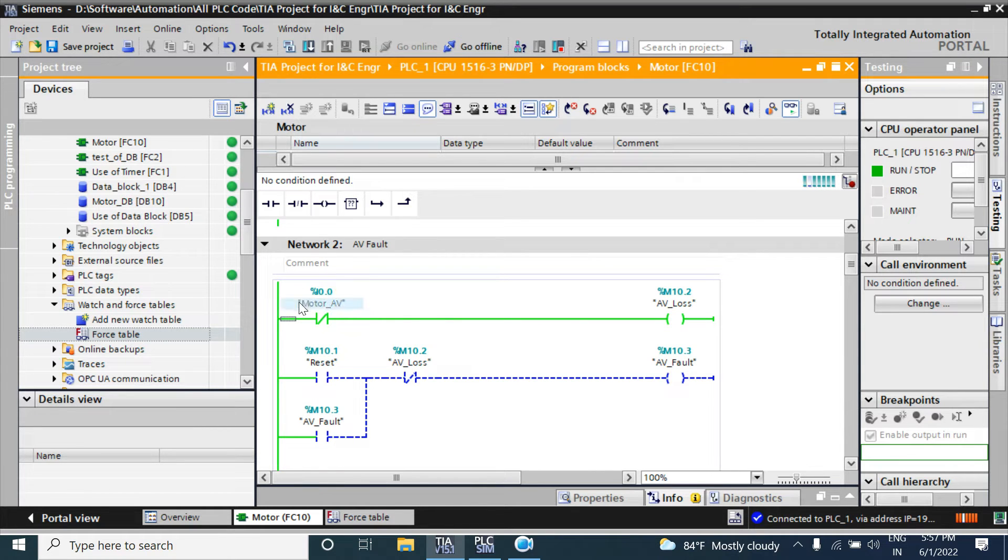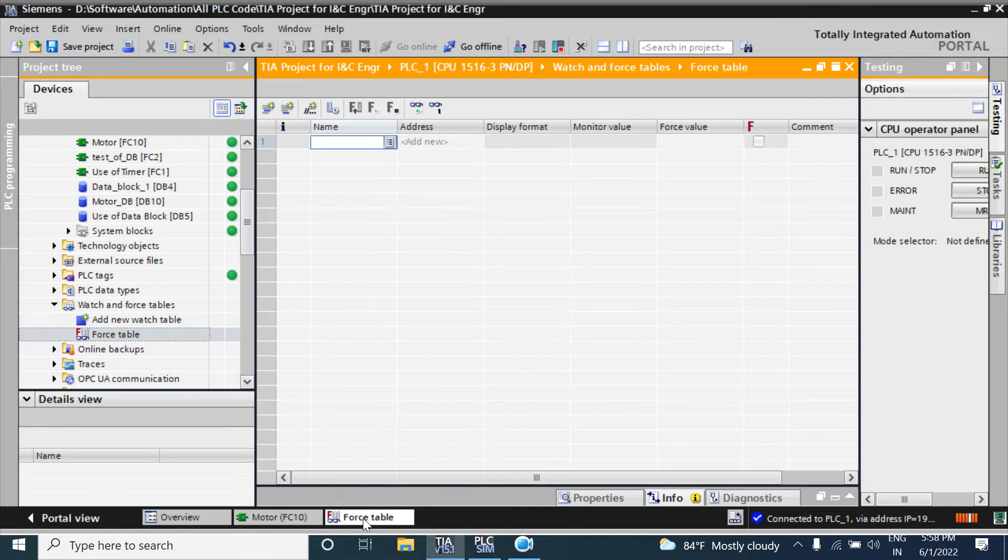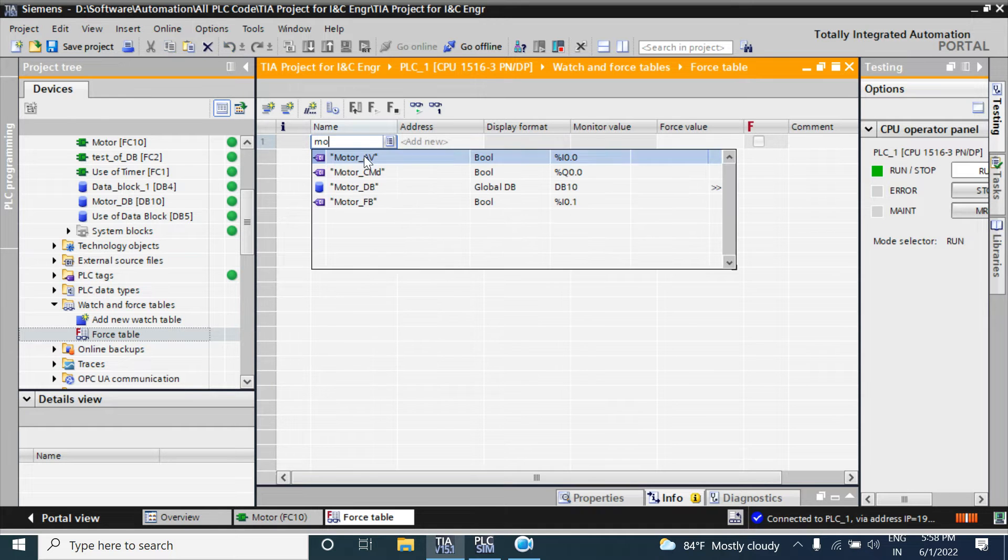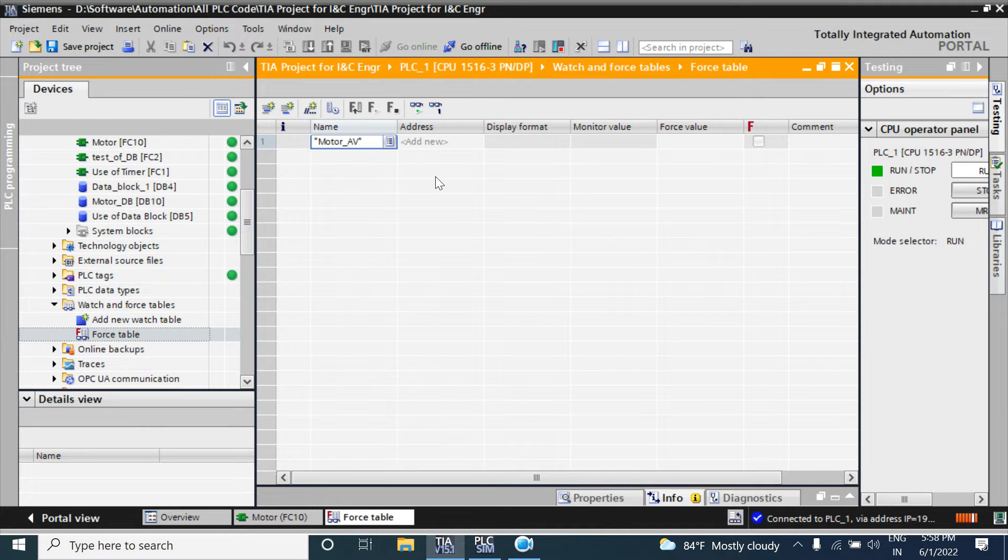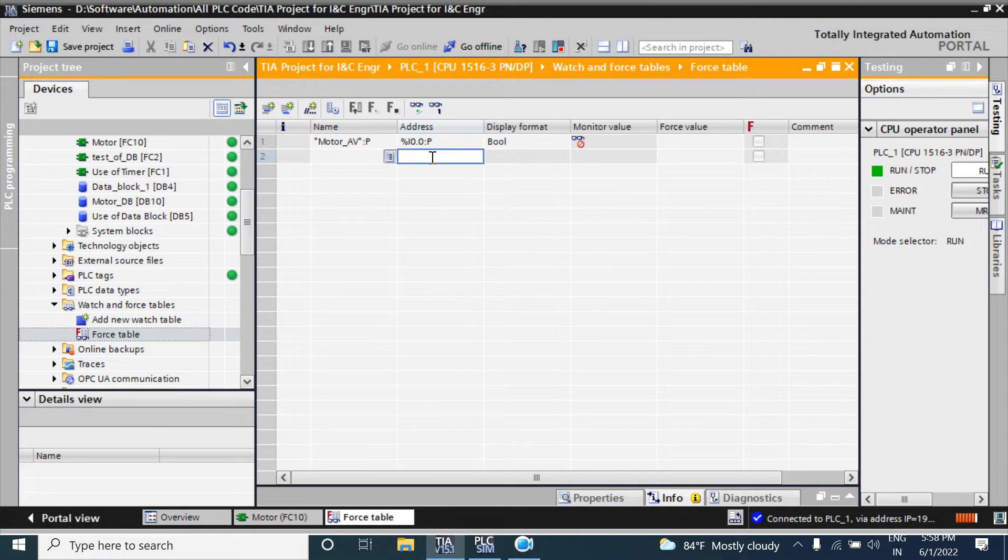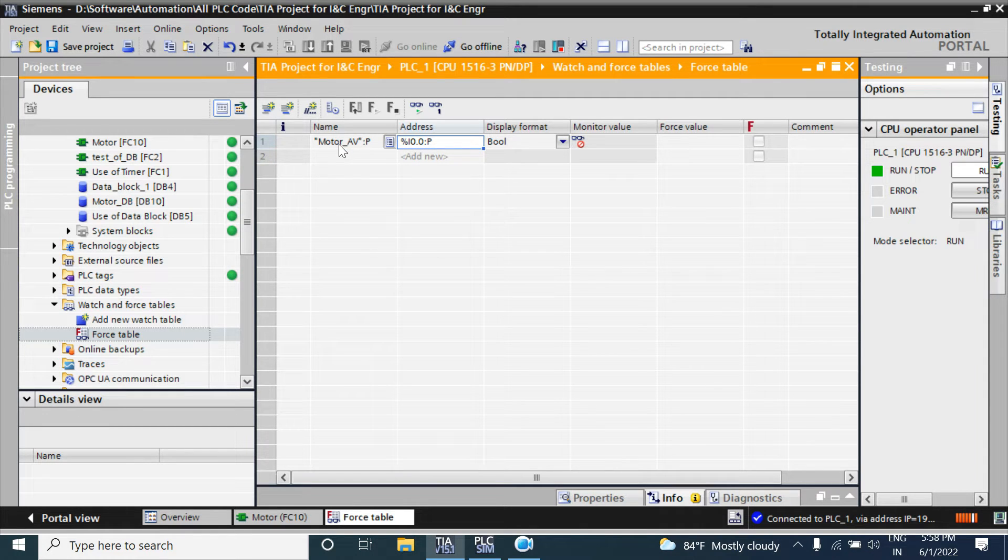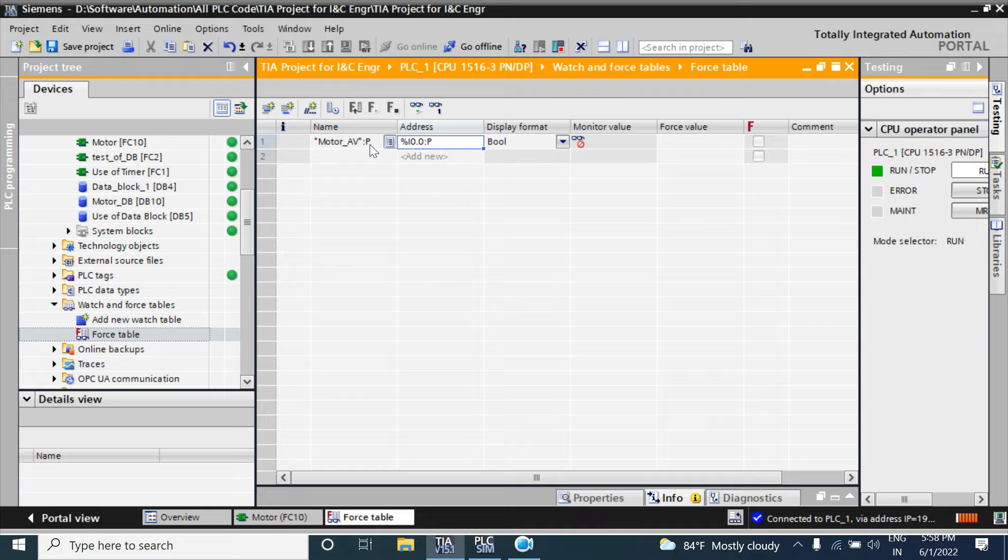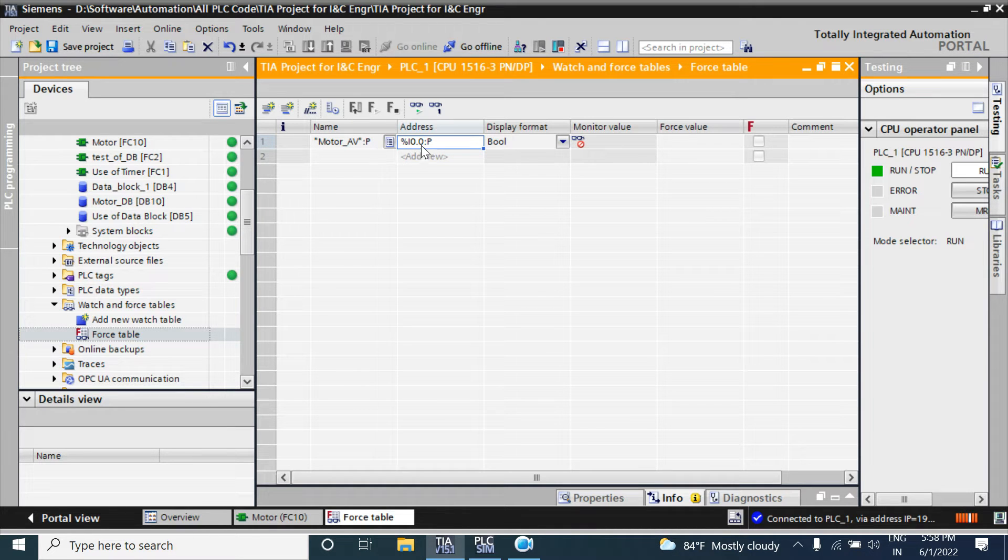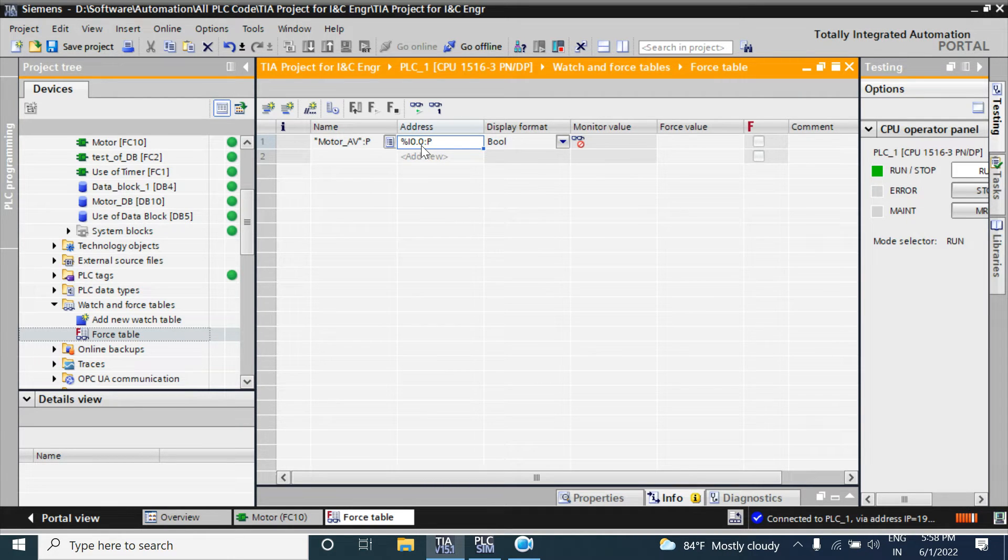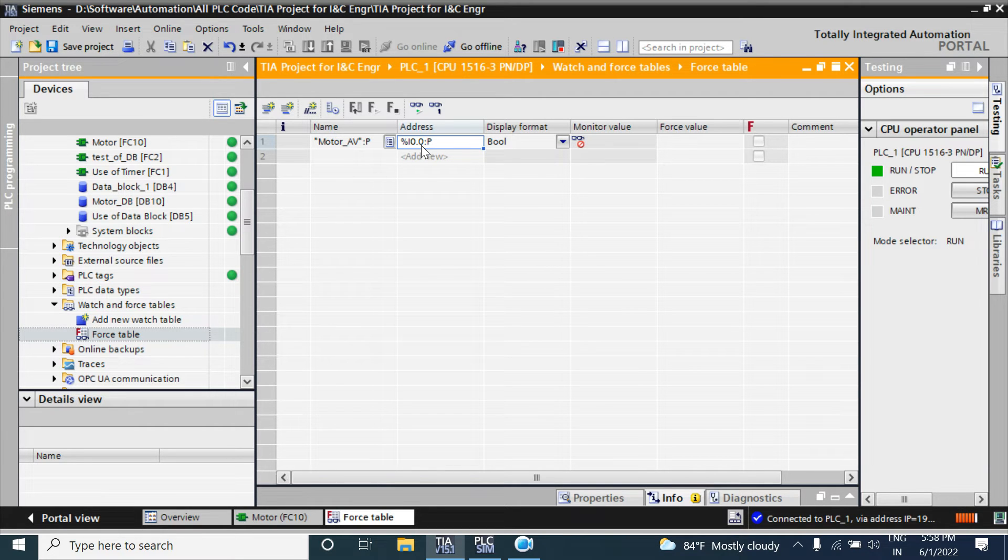I am adding the motor_AV tag, which has address I:0.0. You can write motor here, or we can write directly the input address. Motor_AV is the tag, but the colon P indicates that this I/O is a physical periphery I/O, a physical input, not a memory input or a variable in the data block. It is a physical input periphery.